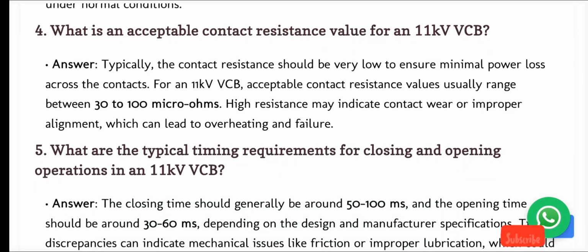4. What is an acceptable contact resistance value for an 11 kV VCB? Answer. Typically, the contact resistance should be very low to ensure minimal power loss across the contacts. For an 11 kV VCB, acceptable contact resistance values usually range between 30 to 100 microohms. High resistance may indicate contact wear or improper alignment, which can lead to overheating and failure.